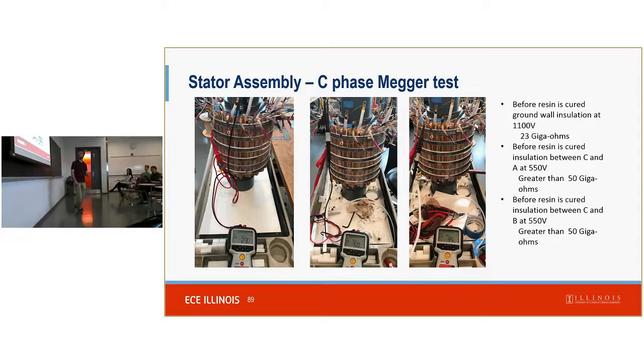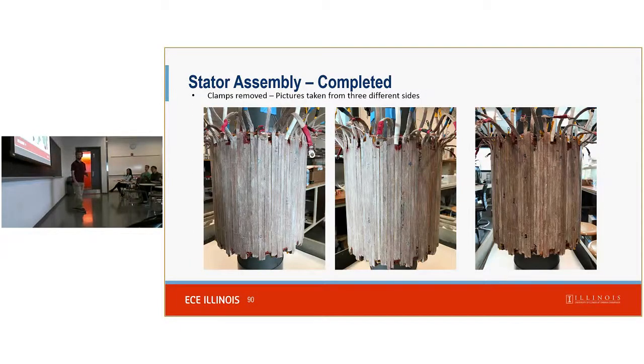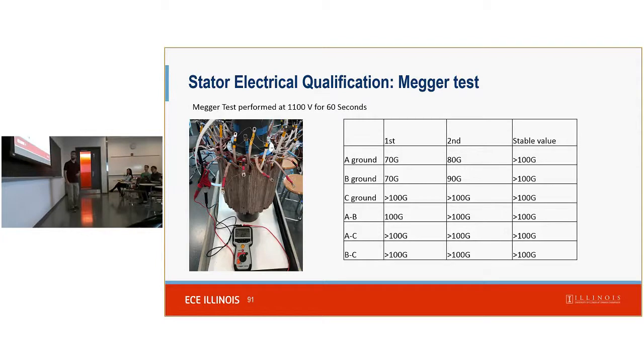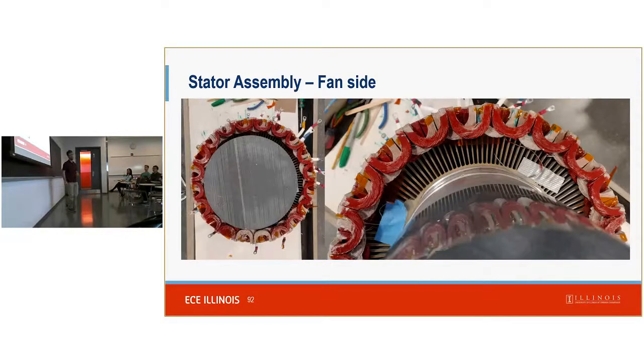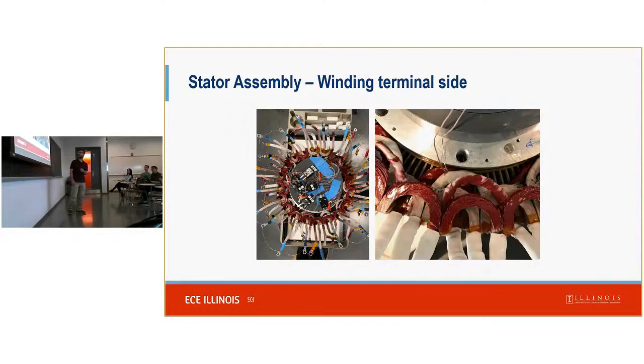Okay. And doing the electrical testing for each set. So here is a picture showing different sides of the completed stator with all of the windings attached. And the results after testing the insulation of all of them were very high resistance, indicating that the insulation was succeeding, was doing what we needed to. And these are a couple close-up pictures. This is on the fan side, so the outlet side. And this, you can see, is the side with all of the leads coming out.